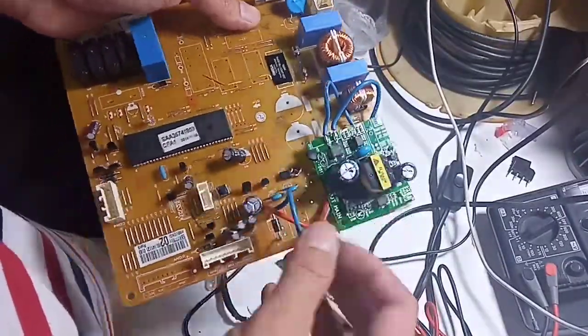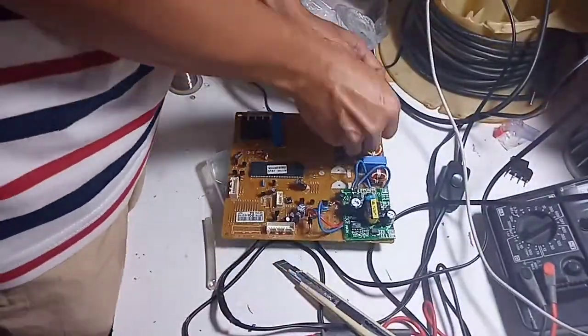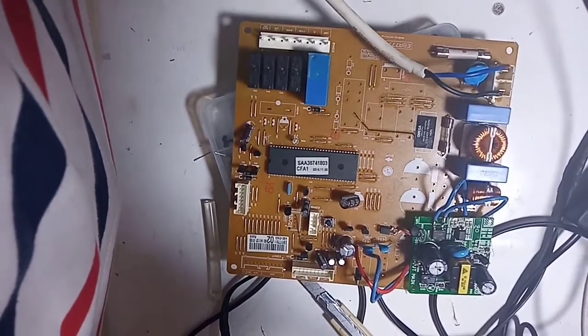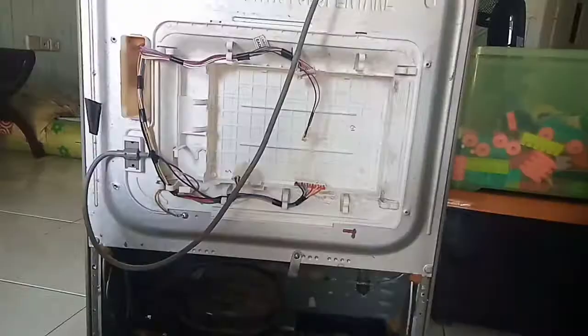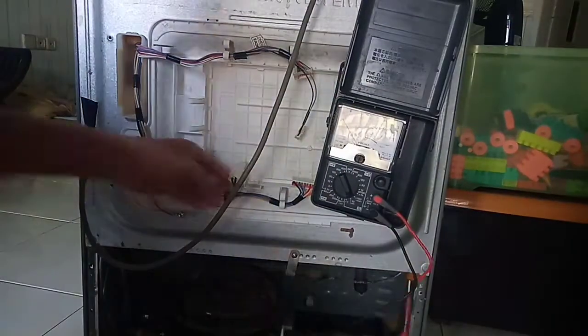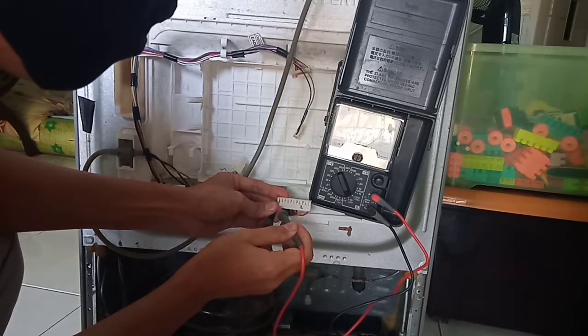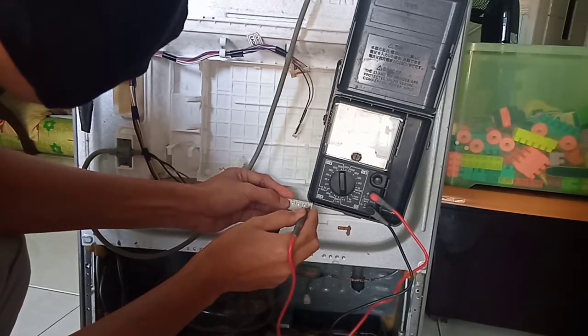Ini penampakan setelah dicangkok. Lilitan-lilitan utamanya tidak dicopot karena masih dipakai untuk direct ke kompresor. Yang diganti mulai dari dioda bridge ke belakang. Langsung kita tes: colokkan, lampu LED sudah berkedip, output sudah keluar 12V. Sebelum dipasang ke unitnya, sebaiknya kita cek dulu area kompresor, heater, dan kipas menggunakan multitester skala ohmmeter untuk memastikan tidak ada yang short.